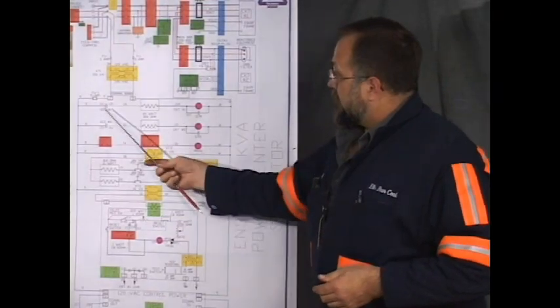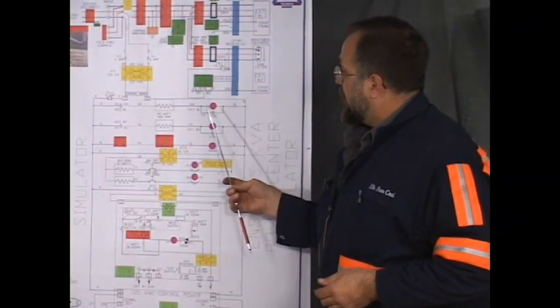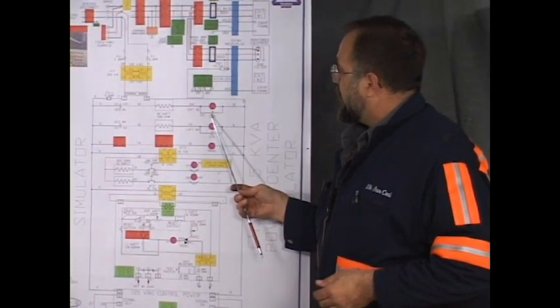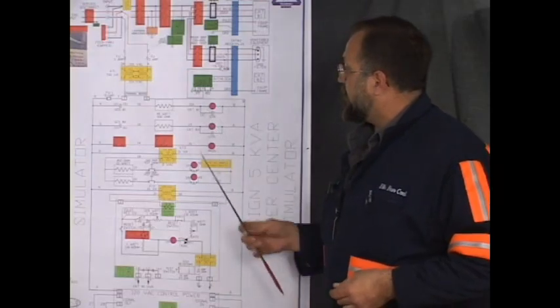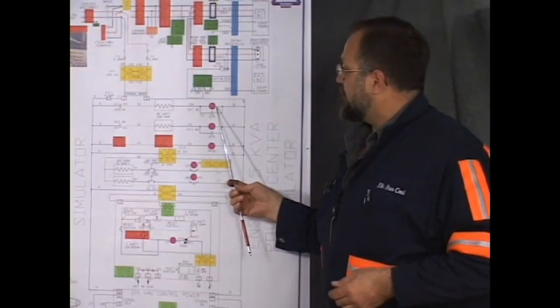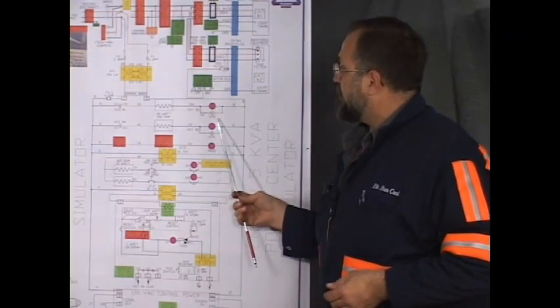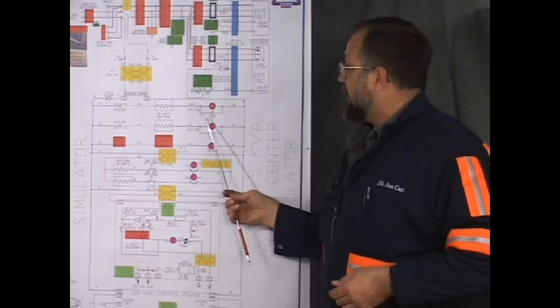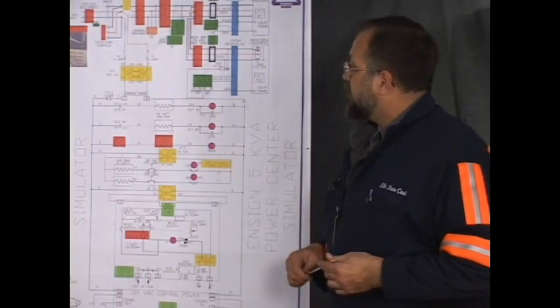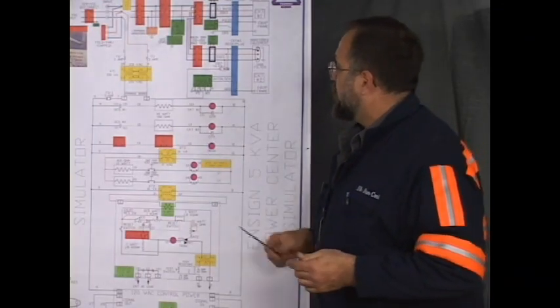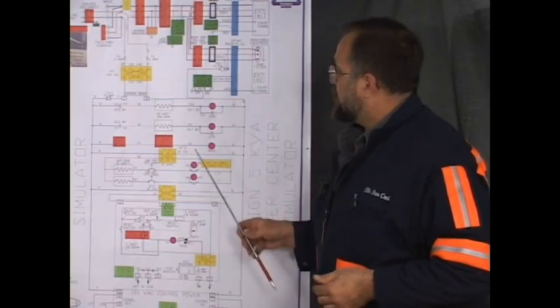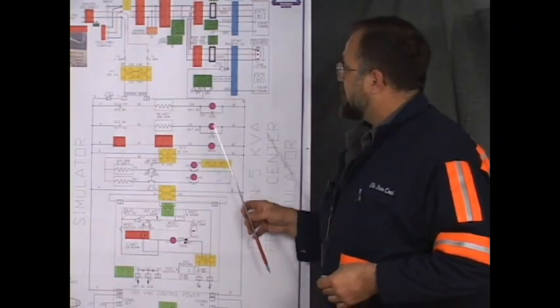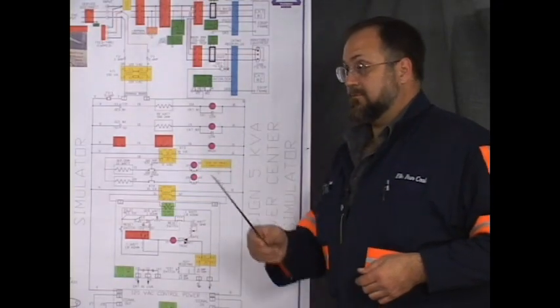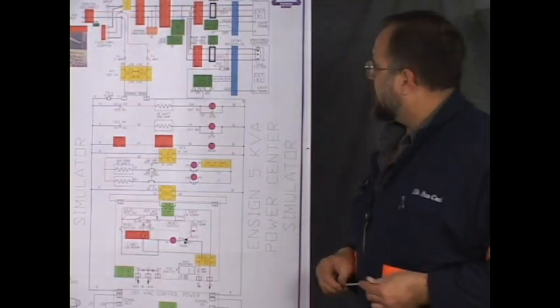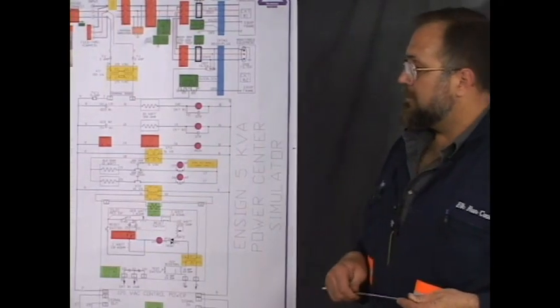After you understand how the circuit works, you know that in order for the GTR to trip this breaker by robbing the power from the UVR, it has to be connected in a circuit with wire. So that's what we're going to check first. We're going to make sure that the GTR, the ground trip relay, is indeed connected to the circuit. And to do that, we're going to make some continuity tests over here.